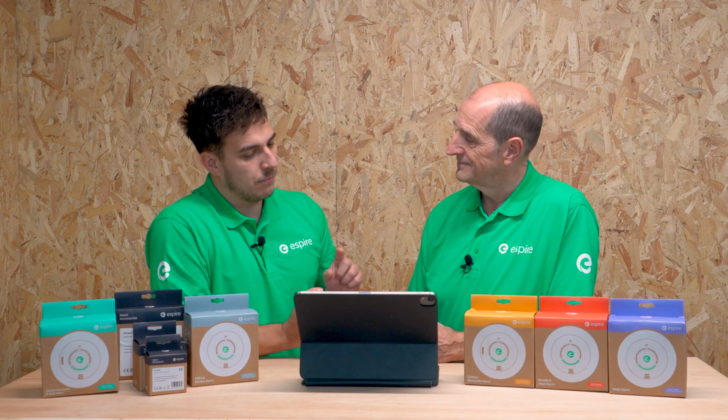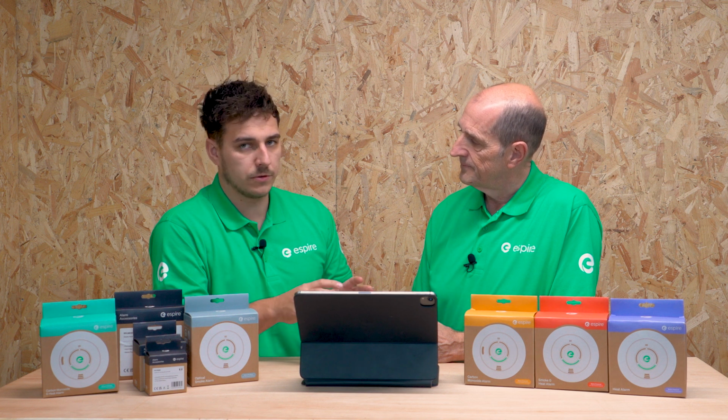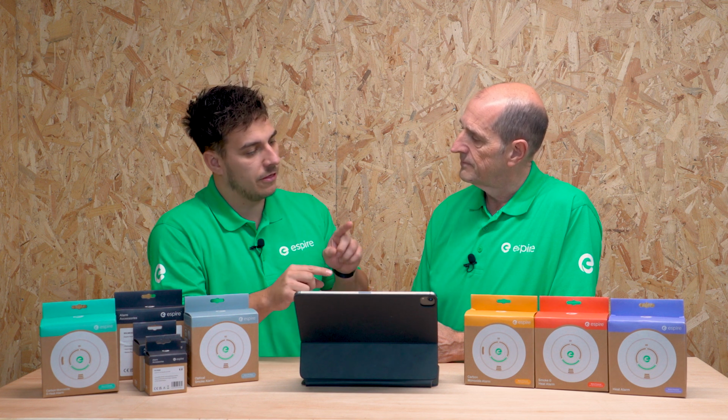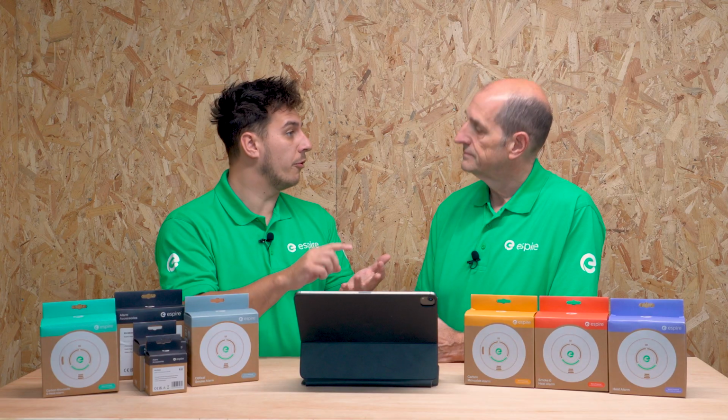So BS 5839 Part 6, Tim, we have gradings in there. Now, I know that this is not quite the same when it comes to carbon monoxide detection, but we do see the battery and the mains. So is there a reason why we need to think about it when maybe we're introducing it into a D1 or an F1 type of system when it comes to 5839 Part 6? What do we need to consider? Yeah. I think that's perfectly fair. If you've got a D1 system that's being installed, then you really want to be selecting a carbon monoxide alarm for a D1 system. The things hang together, and if it's simply battery powered and you're into an F1 system, then you would select an F1 arrangement quite simply for that reason.